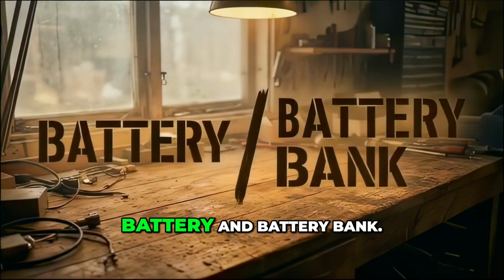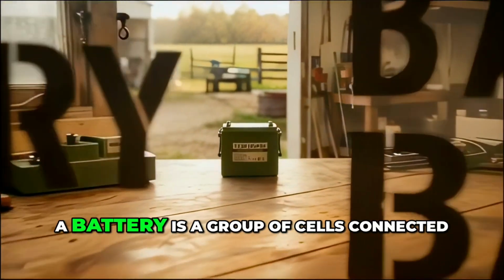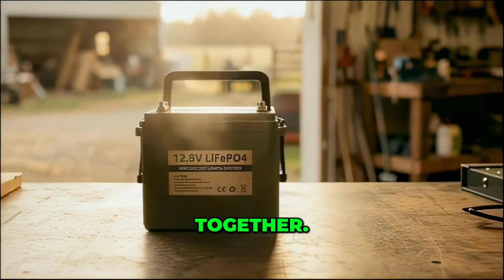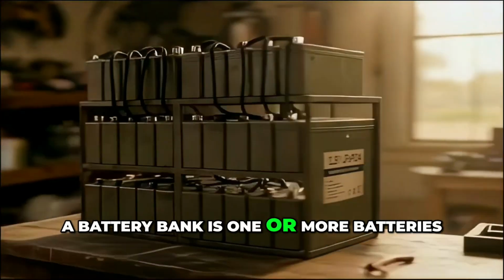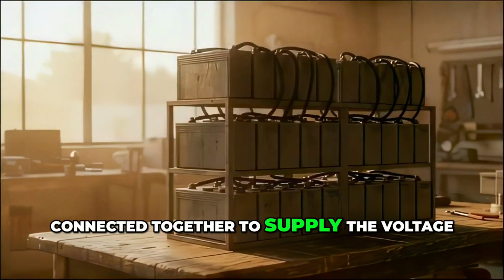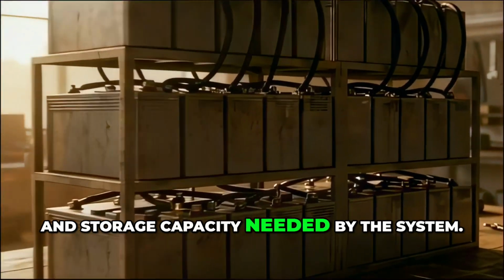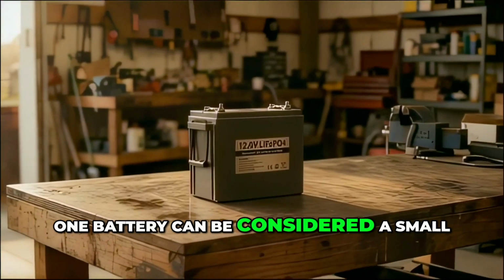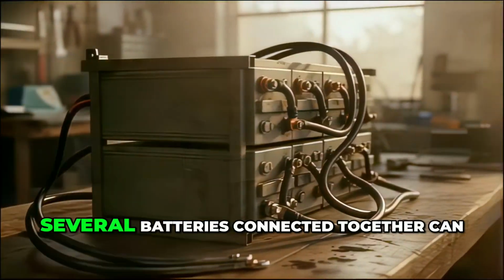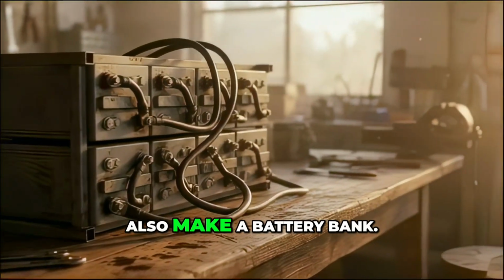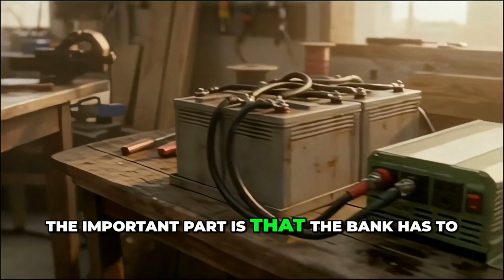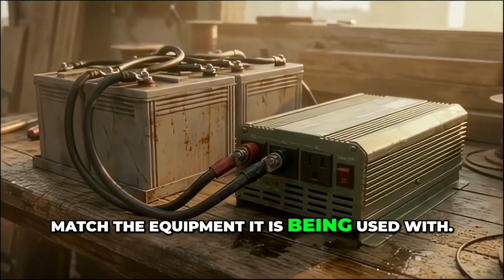Now we need to separate the words battery and battery bank. A battery is a group of cells connected together. A battery bank is one or more batteries connected together to supply the voltage and storage capacity needed by the system. One battery can be considered a small battery bank. Several batteries connected together can also make a battery bank. The important part is that the bank has to match the equipment it is being used with.